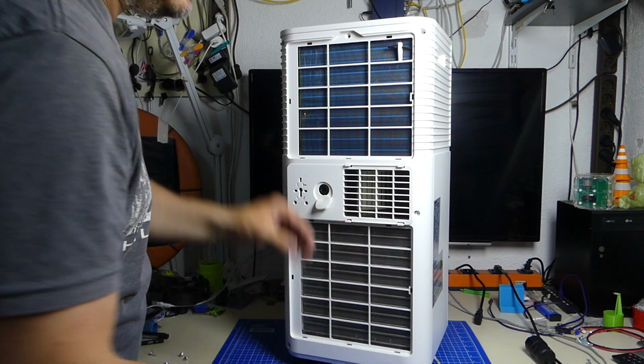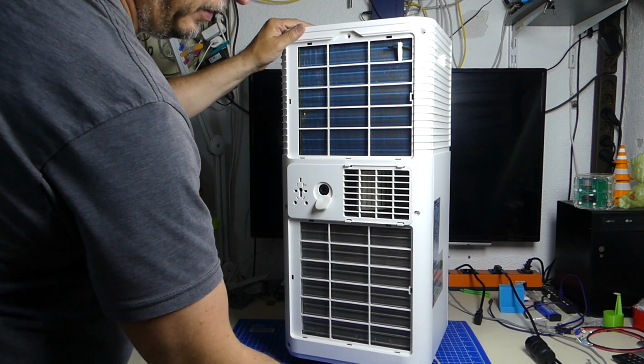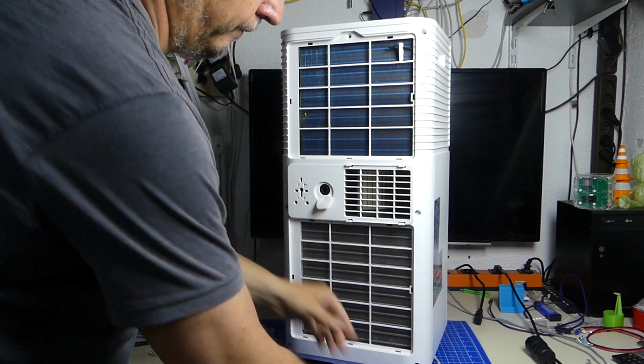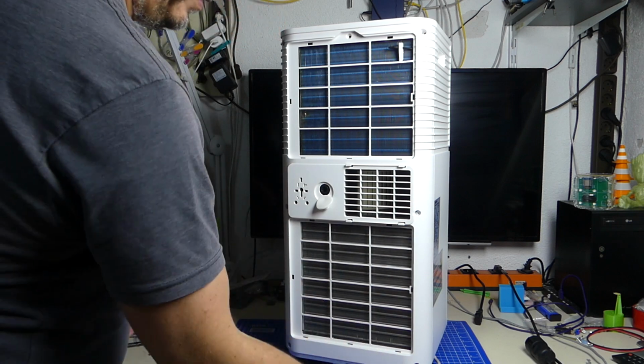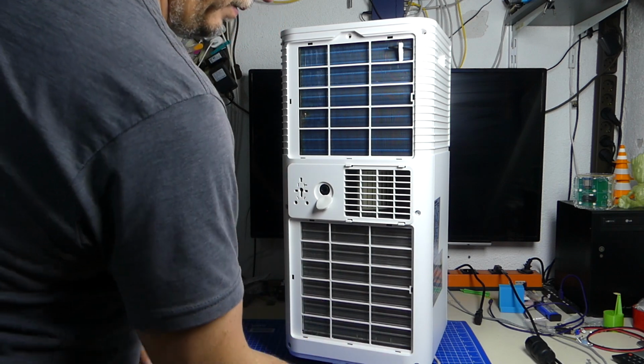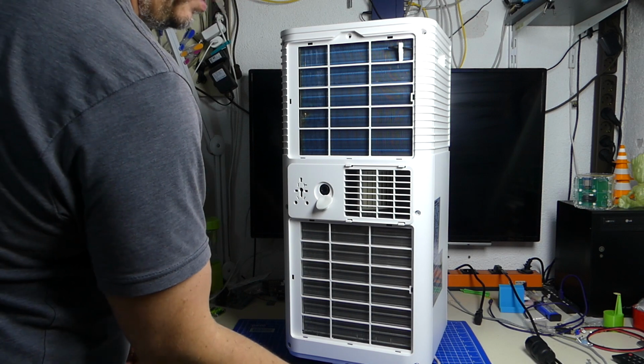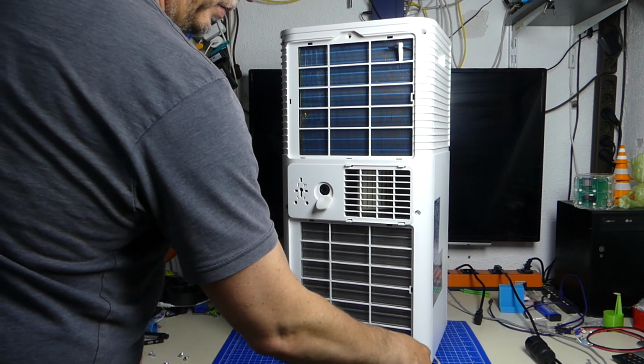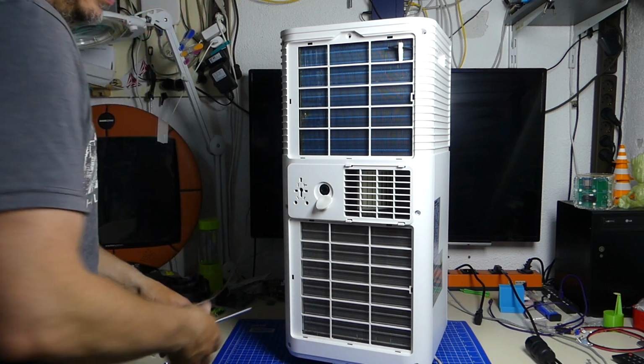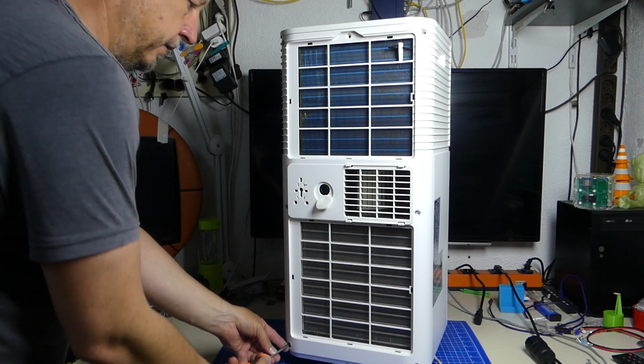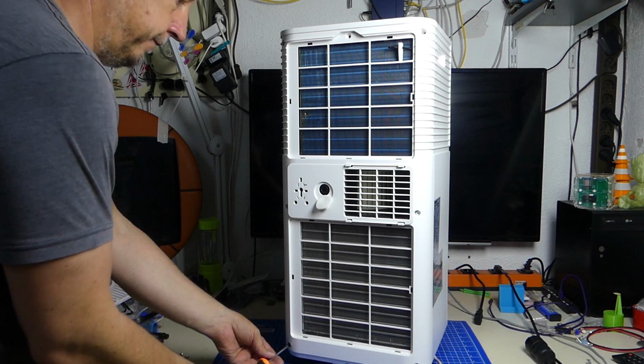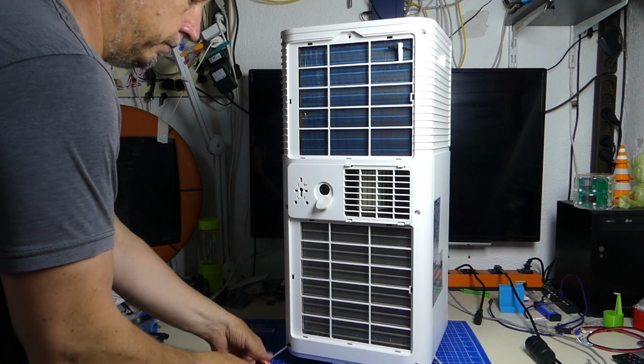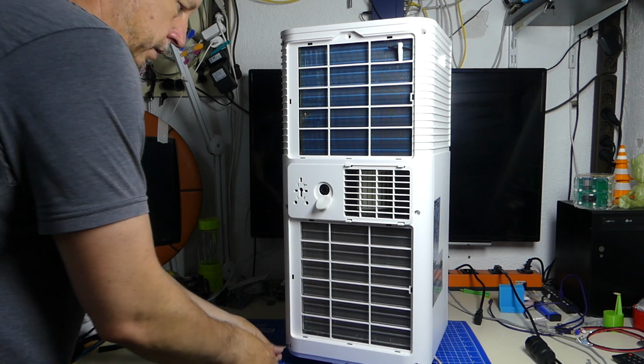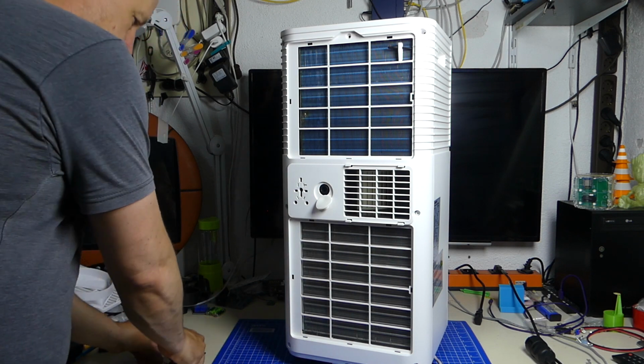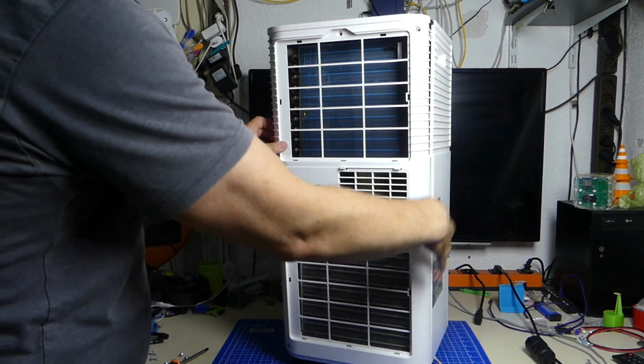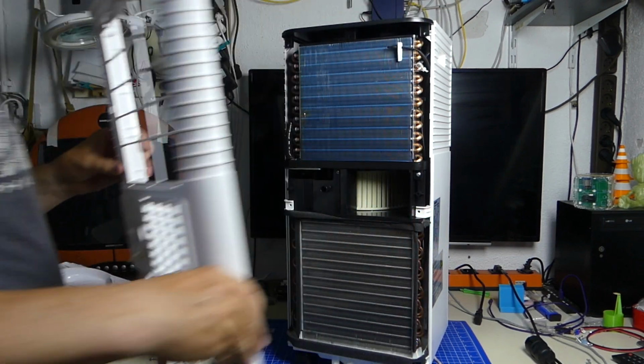And well, that's something that doesn't happen that much. Also, the compressors themselves become smaller and smaller. They still produce quite a lot of heat, and then you have a lot of stored heat from the compressor in the bottom of the cooler unit, and that's something you don't really want to have.